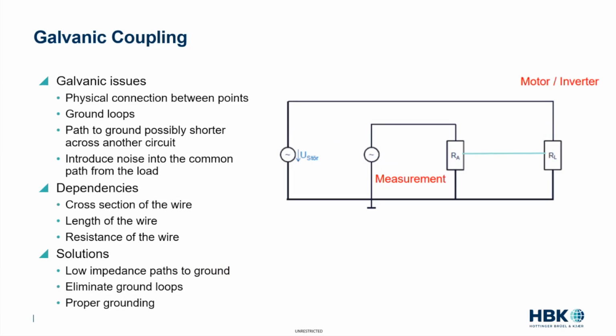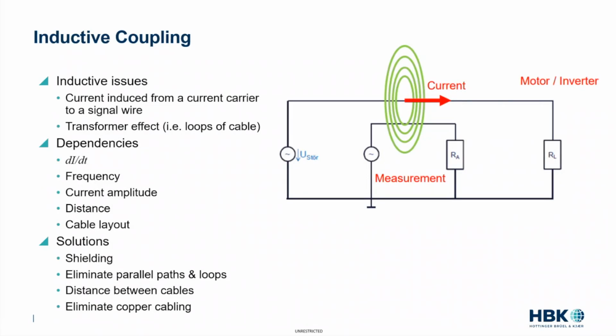Well, basically with galvanic issues, you have the physical connection between points. You also have to deal with ground loops. You've got a path to ground, possibly shorter across another circuit. You also have the introduction of noise into the common path from the load. So it's dependent on the cross-section of the wire, the length, and the resistance of the wire. And some solutions include low impedance paths to ground, elimination of ground loops, and proper grounding. But later on in this webinar, we'll talk about some ultimate solutions to conquer and mitigate these issues. So that's coming up later in this webinar.